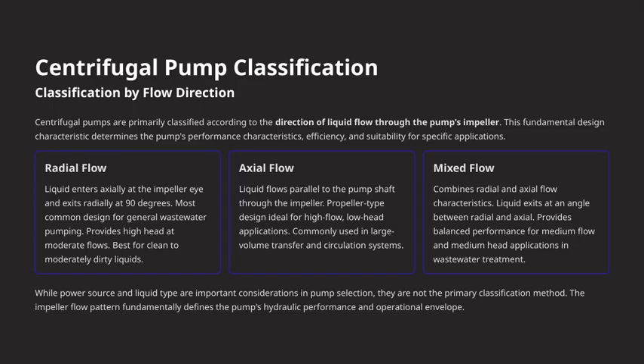Then we have mixed flow pumps. As the name suggests, they combine features of both radial and axial flow. The liquid exits at an angle somewhere between radial and axial, providing a balanced performance. These are suitable for medium flow and head applications, often found in wastewater treatment where versatility is key.